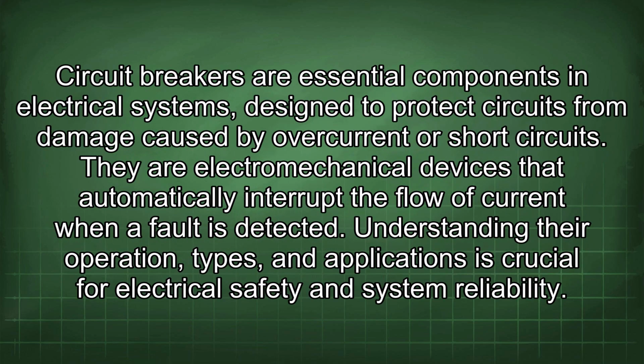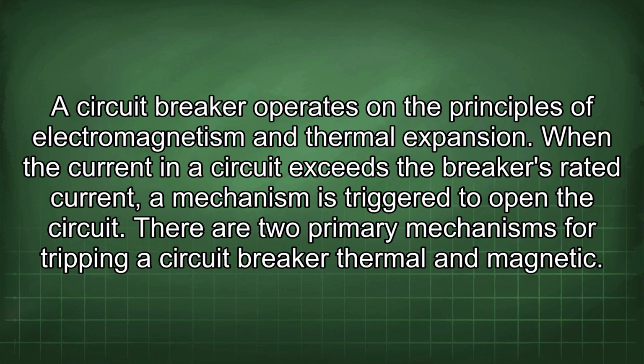Circuit breakers are essential components in electrical systems, designed to protect circuits from damage caused by overcurrent or short circuits. They are electromechanical devices that automatically interrupt the flow of current when a fault is detected. Understanding their operation types and applications is crucial for electrical safety and system reliability. A circuit breaker operates on the principles of electromagnetism and thermal expansion. When the current in a circuit exceeds the breaker's rated current, a mechanism is triggered to open the circuit.